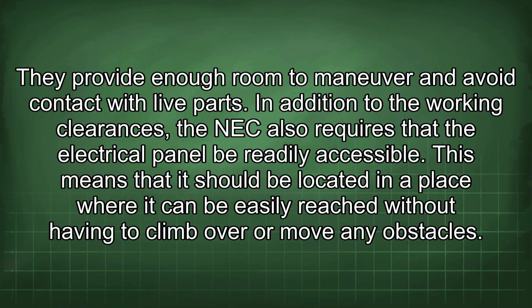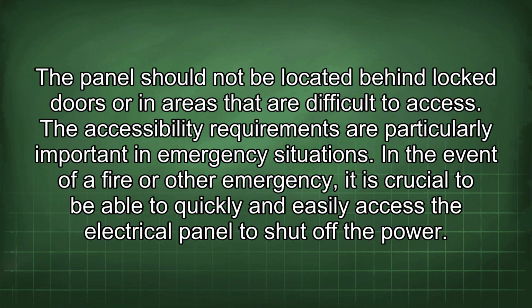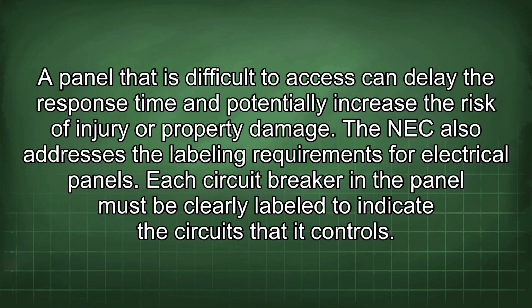In addition to the working clearances, the NEC also requires that the electrical panel be readily accessible. This means that it should be located in a place where it can be easily reached without having to climb over or move any obstacles. The panel should not be located behind locked doors or in areas that are difficult to access. The accessibility requirements are particularly important in emergency situations. In the event of a fire or other emergency, it is crucial to be able to quickly and easily access the electrical panel to shut off the power.